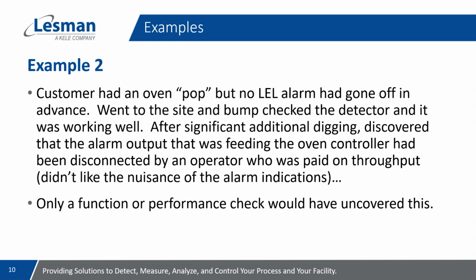Example 2 is a little bit scary because it hits close to home. We measure LEL levels inside drying ovens. This is a relatively new system. When we put it in, as we do with all startups, we checked everything right down to the interlocks. About a year after we installed the system and commissioned it, I got a frantic call from a customer that they had an event and that my gas detector didn't work. I dropped everything, grabbed my calibration equipment, and rushed over to the site. When I got there, everybody was on pins and needles, and I got the distinct impression that the assumption was my system had failed. For reference, the event had resulted in a blowout panel on the ductwork leaving its location.